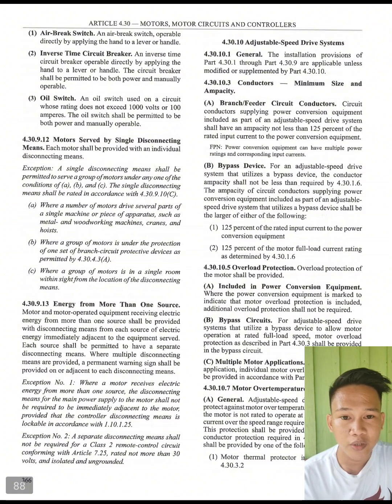So, ngayon po na exemption. Exemption number 1, where a motor receives electric energy from more than one source. The disconnecting means for the main power supply to the motor shall not be required to be immediately adjacent to the motors, provided that the controller disconnecting means is lockable in accordance with 1.10.1.25. So, exemption number 2. A separate disconnecting means shall not be required for a Class 2 remote control circuit conforming with Article 7.25, rated not more than 30 volts and isolated and ungrounded.